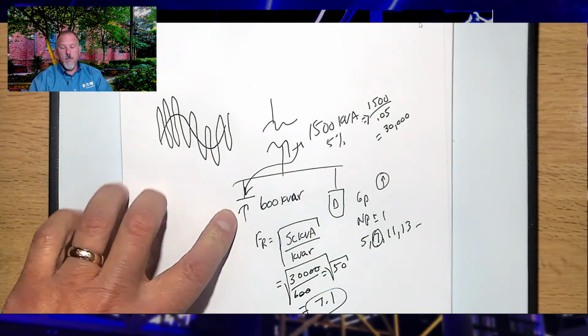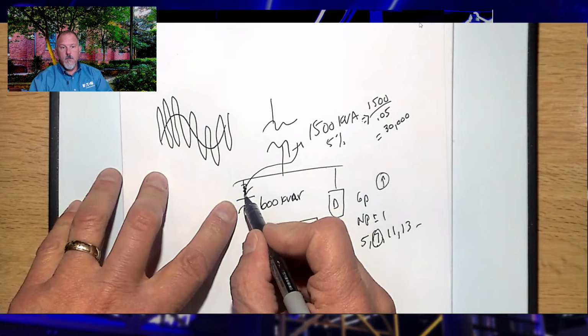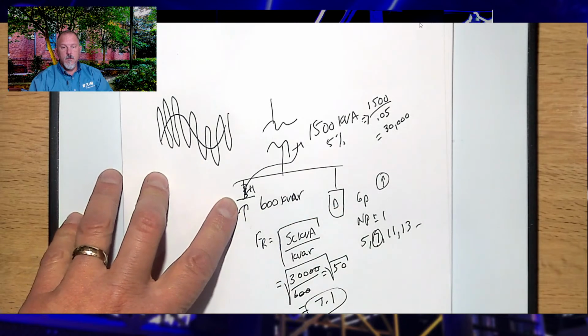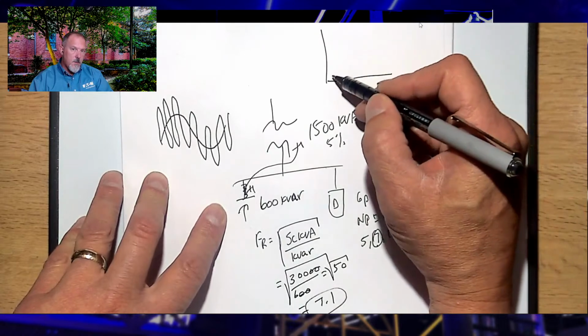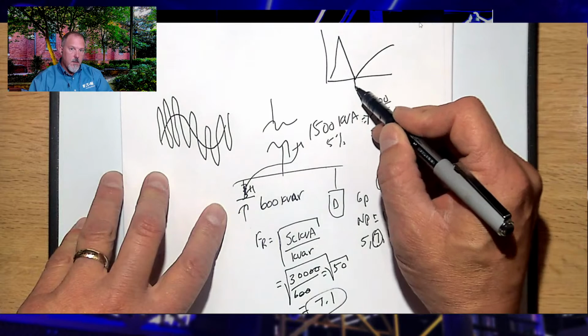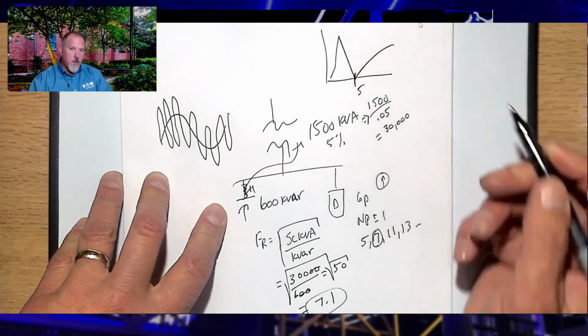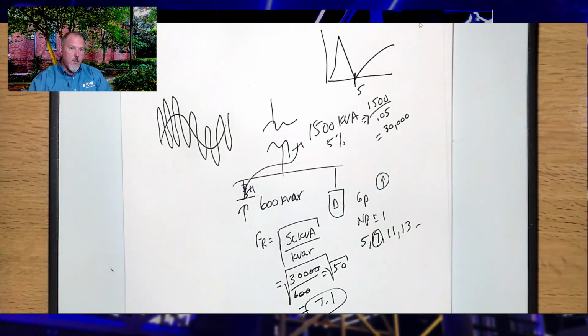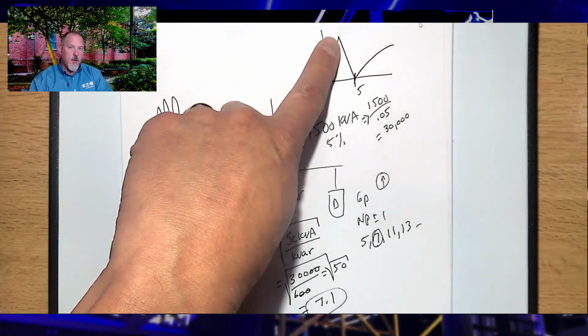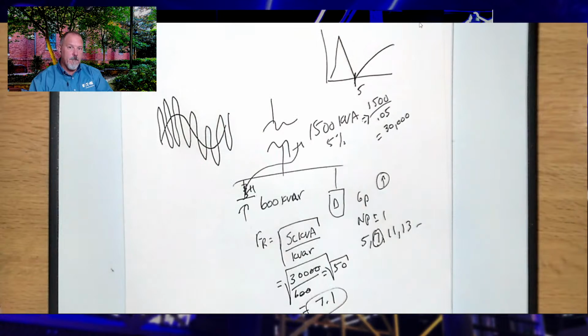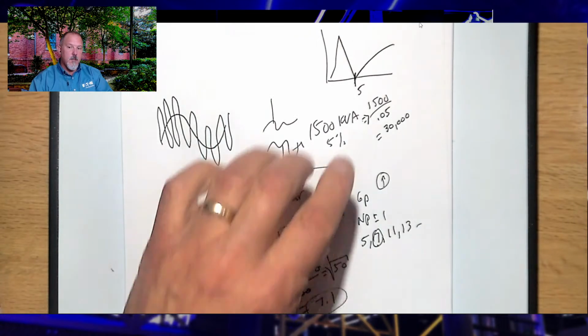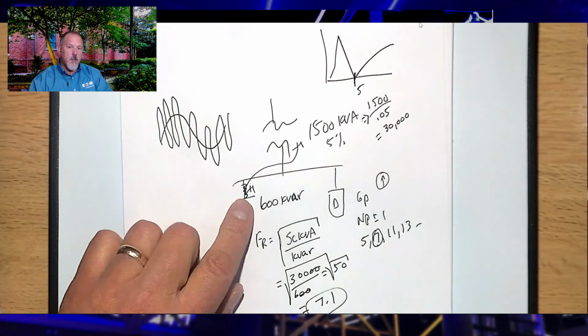So when that happens, what you typically would do is make this into a harmonic filter. Remember, a harmonic filter has a parallel resonant point and a series resonant point. If you put the series resonant point at the lowest harmonic that you would expect, the fifth harmonic, then look where your parallel resonant point is. It's below any harmonics that you'll ever see. So you never have to worry about it. And that's an oversimplification of how you design filters. But you can make that capacitor into that.